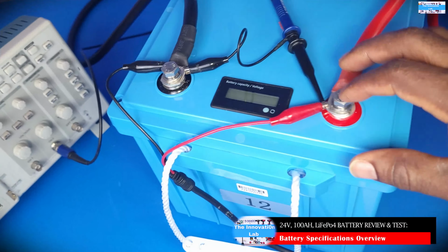As you guys can see here at this instant when we are making the measurement, you can see a battery voltage of 25.80 volts and a load current going from the battery system to the power inverter system of 37.17 amps. So when you do the math at this instant, what you're supposed to see is right around 959 watts. So all I had to do was keep an eye on the system and periodically check on it so I could capture the discharge response of the battery system at different time intervals. And in the very end, I was able to capture a time lapse of the system so I can show you guys what happened at the very end when the BMS of the battery system turned off the load so as to protect the battery system from over discharging.